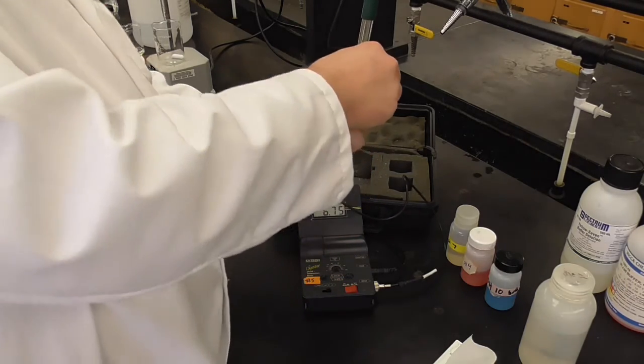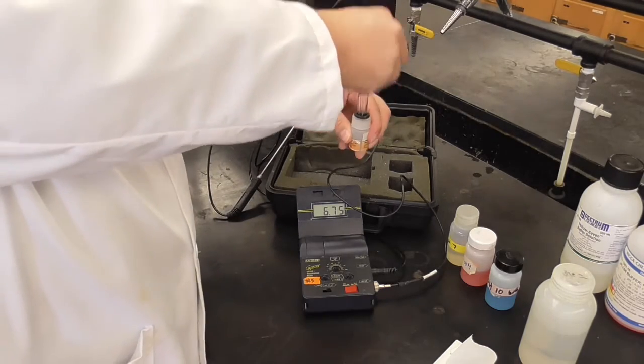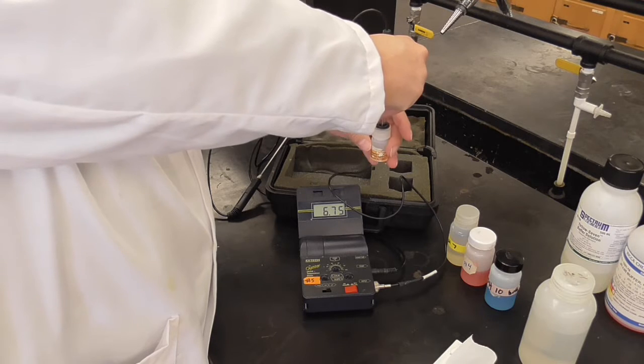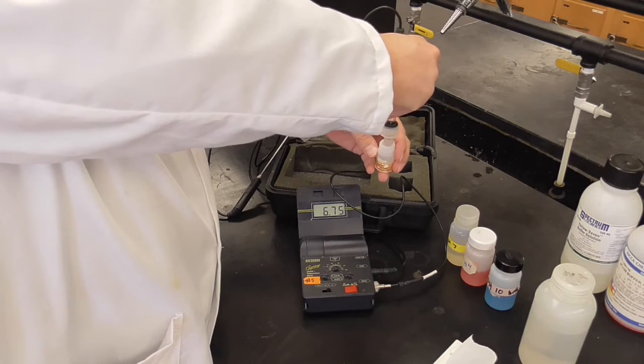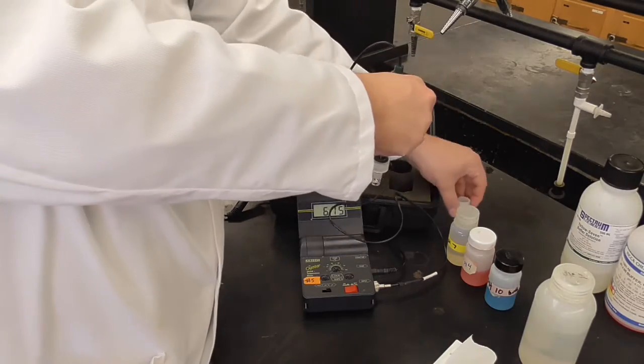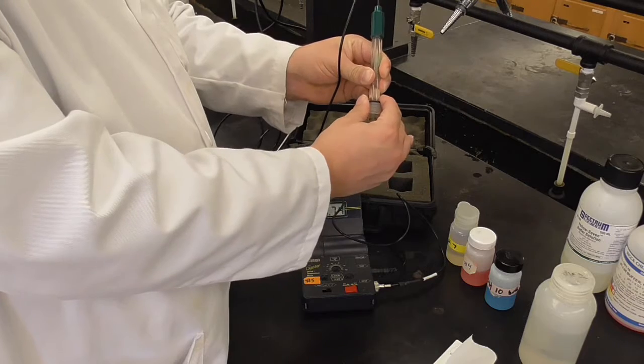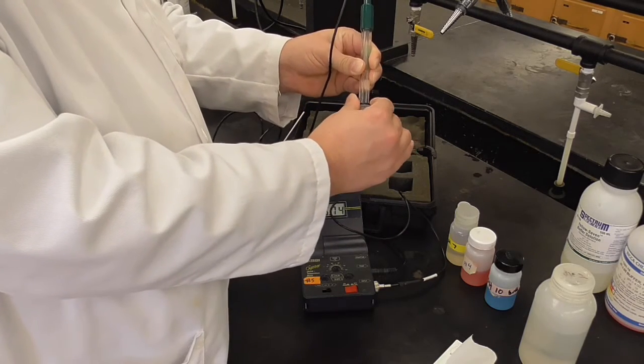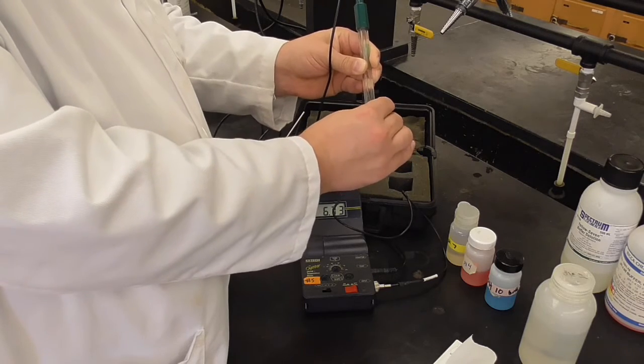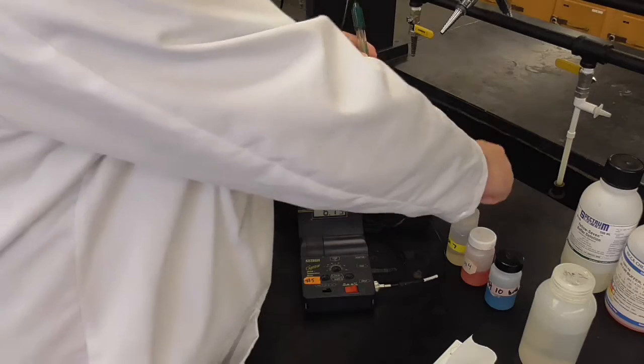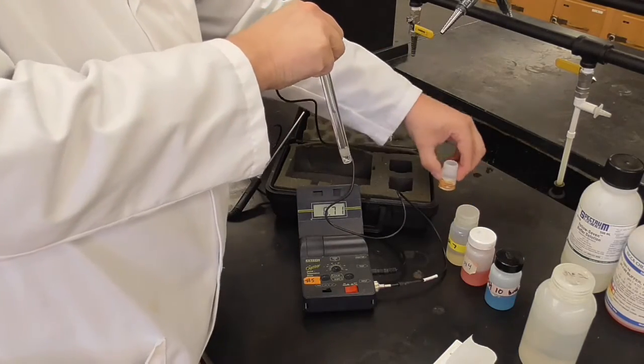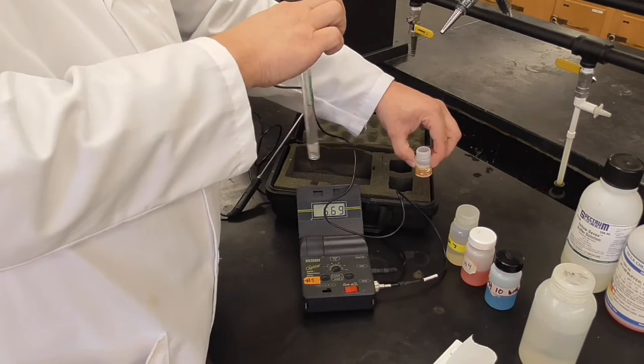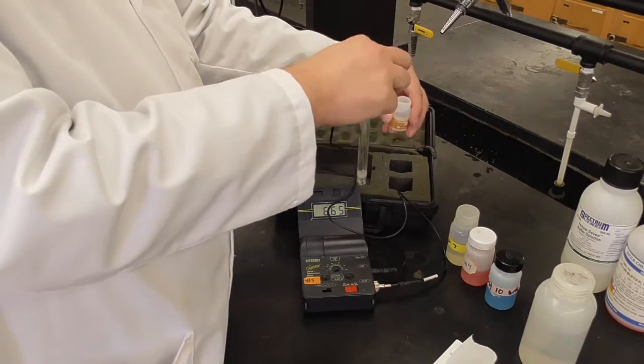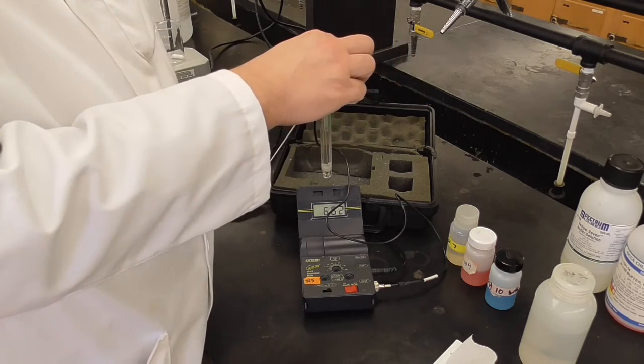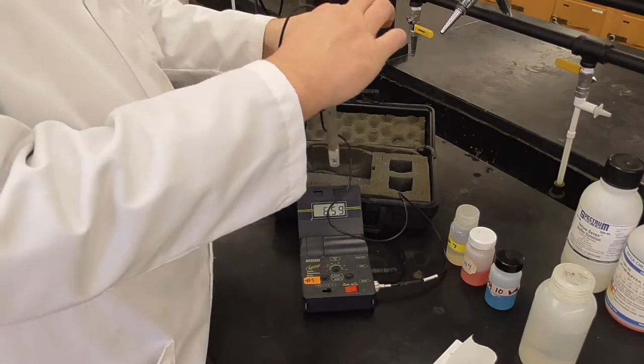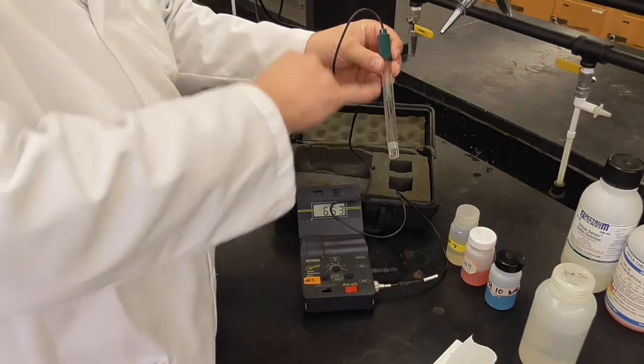And so I unscrew the vial. Maybe there we go, so we can see it hopefully. So I'm unscrewing the vial here, or the little container. I'm going to set that down, and now I'm going to take off the top of it here. I find that works better than trying to pull that out of there first, because this way you don't have a whole bunch of solution in there. Then I'm going to take this little thing. It's very easy to knock over, and even if I put the cap on, it obviously has a hole in it because that's where the pH meter goes through. So I usually set it up on top so it's out of the way before we get started.